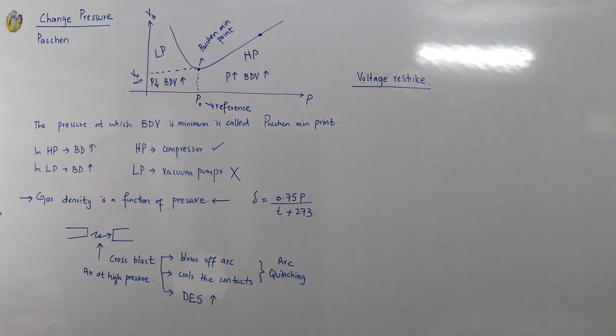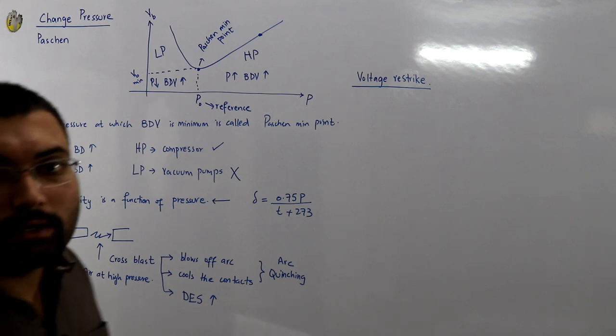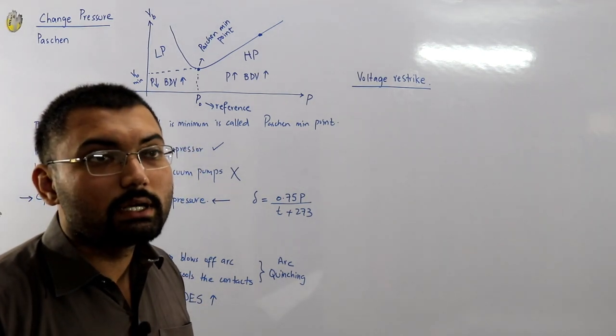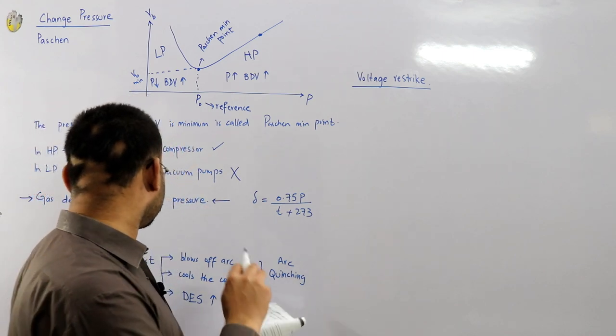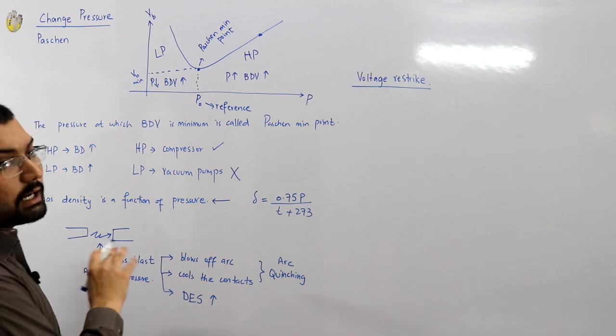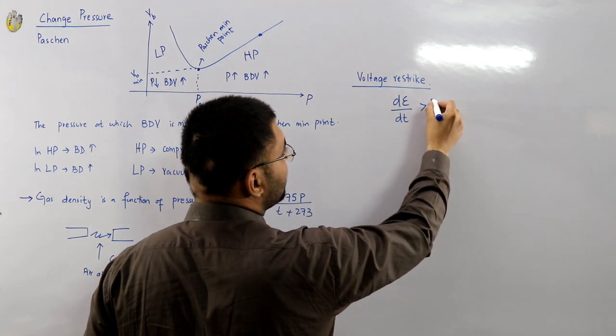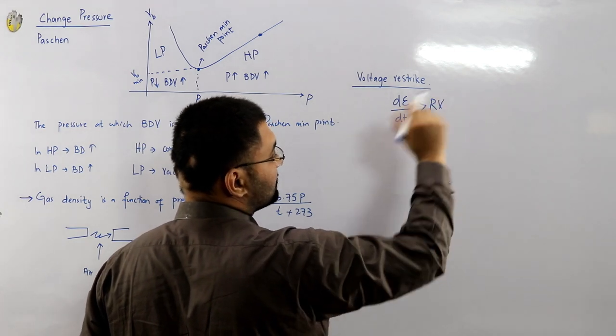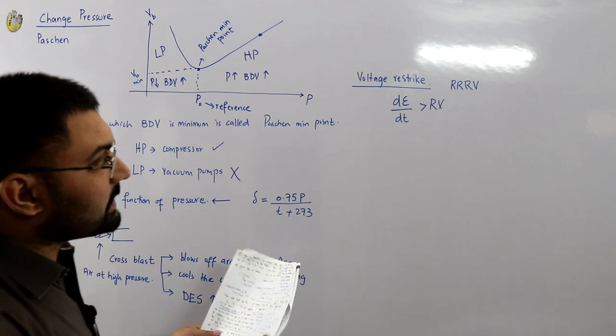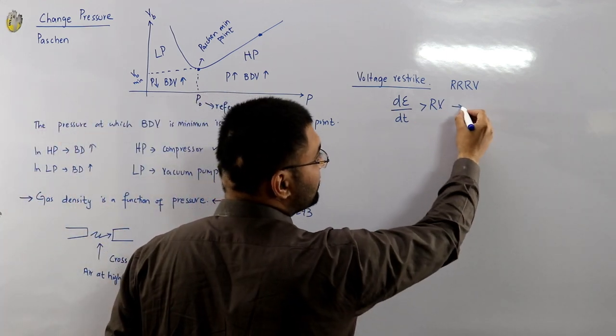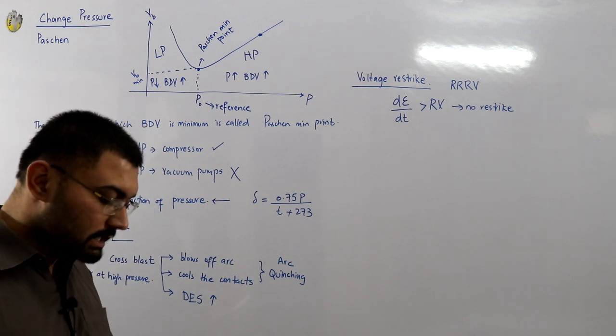For the voltage restrike, you have to provide the air until the contacts are open. When there is a fault and the contacts are open, you have to continuously admit air. The dielectric strength increases when you put in pressurized air, and the rate at which the dielectric strength increases should be greater than the rate of rise of the recovery voltage — written as RRRV. If the rate of dielectric strength increase is greater, then you have no restrike.